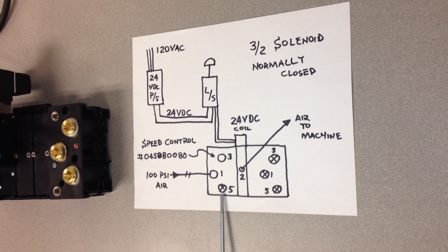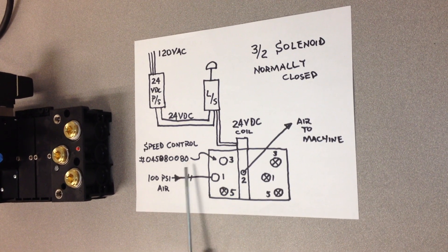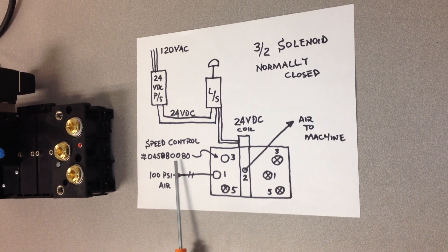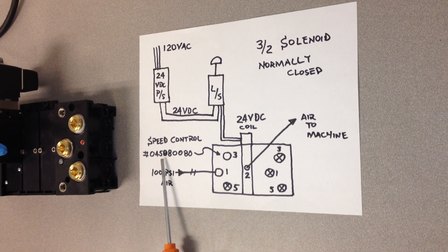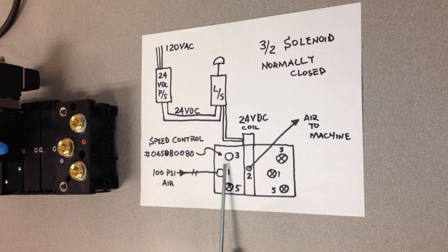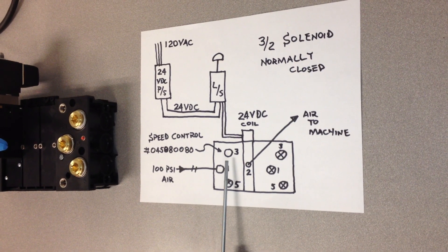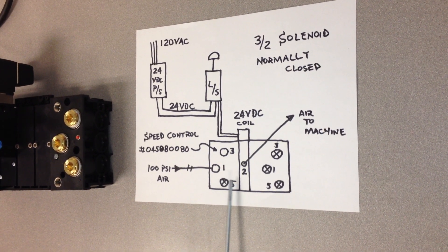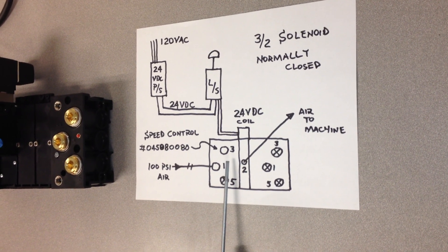Port five is plugged. And in port three, we have something called a speed control, and this comes from applied fluid power. And the part number is 045-08-0080. The reason for having a speed control is we have to have a differential pressure of 27 psi across the solenoid for things to work properly. So that may or may not be required in your application.